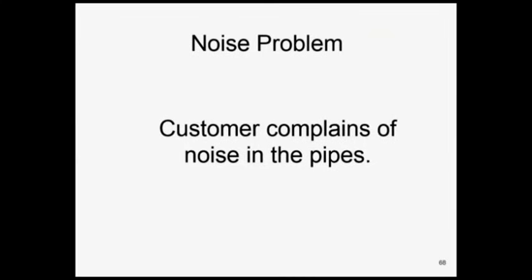Now, you put it in, and you get a call from the owner, a call from the client. He says, my pump is noisy, or my pipes are making a noise, a little high whistle noise going on. Could be air, but could be some other issues as well. But you've got a complaint, so you're going to check it out. Why could you possibly have noise in a pumping system? One possibility would be overpumping. But let's just take a look.